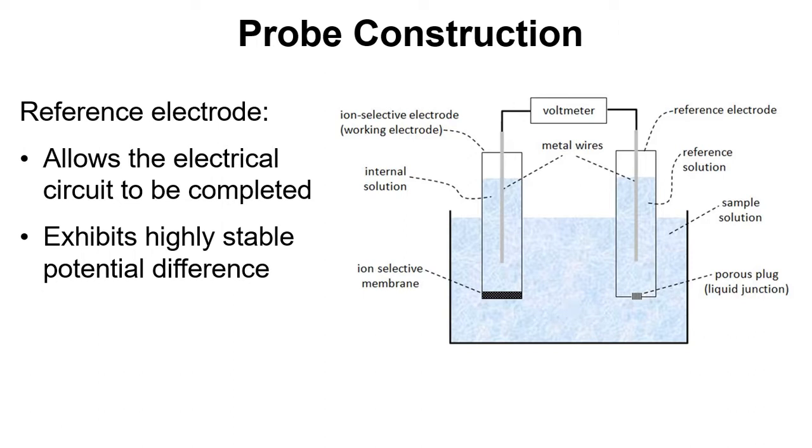Although as we've seen in a previous video that we can get drift over this. But the idea is that we get this stable fixed potential difference between the wire and the sample solution. And we require this reference electrode in order to take readings. If we didn't have this reference electrode, we wouldn't be able to complete the circuit and we wouldn't be able to get a voltage reading for the potential difference of the probe.